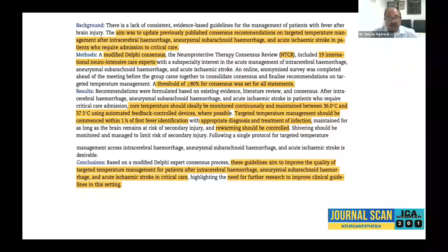The core temperature should ideally be monitored continuously and maintained between 36.0 and 37.5 degrees using an automated feedback control device where possible. Targeted temperature management should be commenced within 1 hour of first fever identification in this group of patients, with appropriate diagnosis and treatment of infections. Any temperature lowering that is done, rewarming should be in a very controlled manner. So based on these, the recommendation on how to use targeted temperature control was that it should be used either continuously or at least hourly, with 100% consensus.